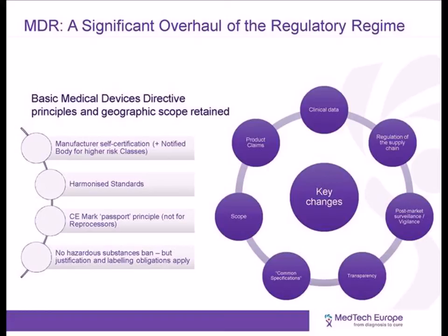Post-market obligations, such as post-market surveillance and safety reporting obligations, are also important. Under the MDR, manufacturers are subject to increased post-market surveillance and more reporting requirements. Submission of adverse event reports, for instance, will become centralized in the future via the EUDAMED Vigilance Portal, which will constitute some changes but should bring some new efficiencies to the reporting system.